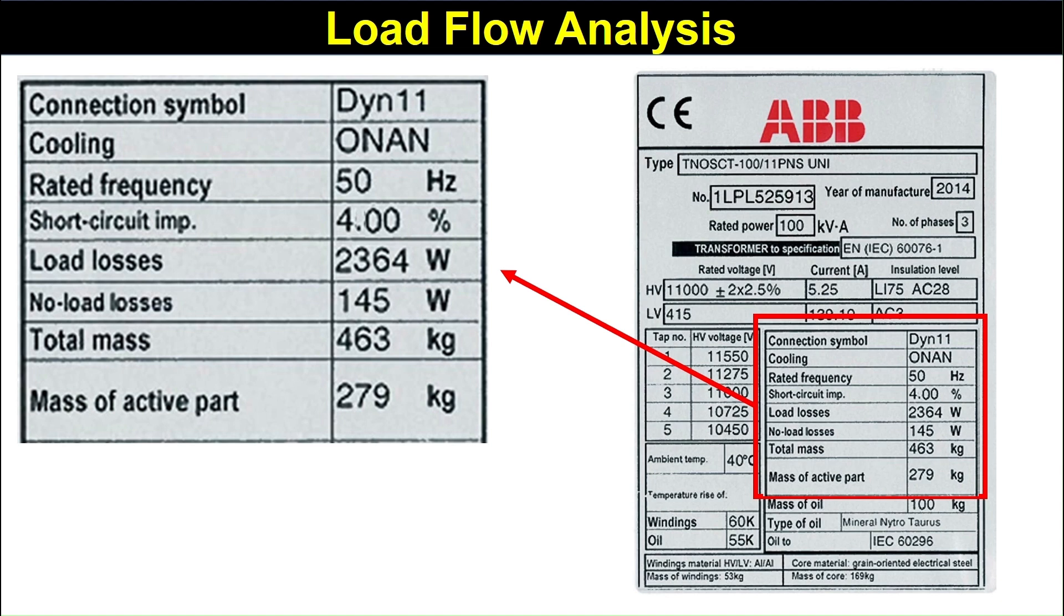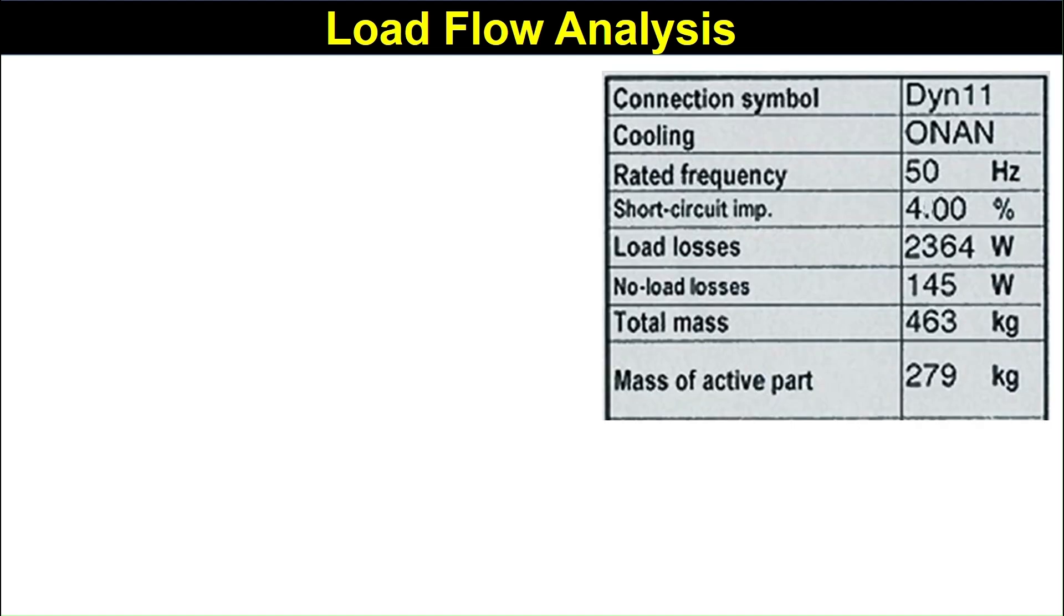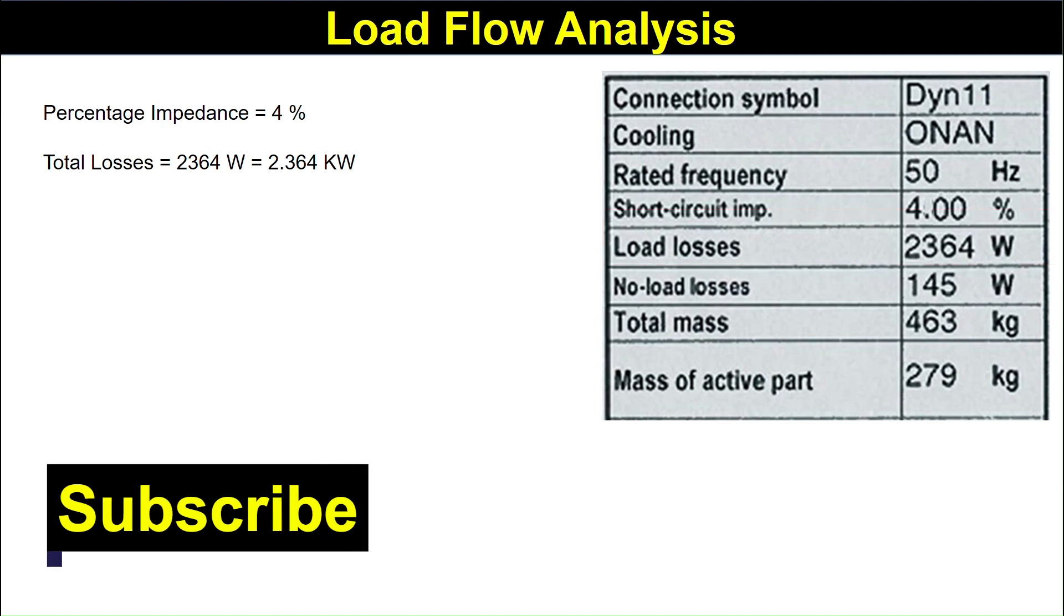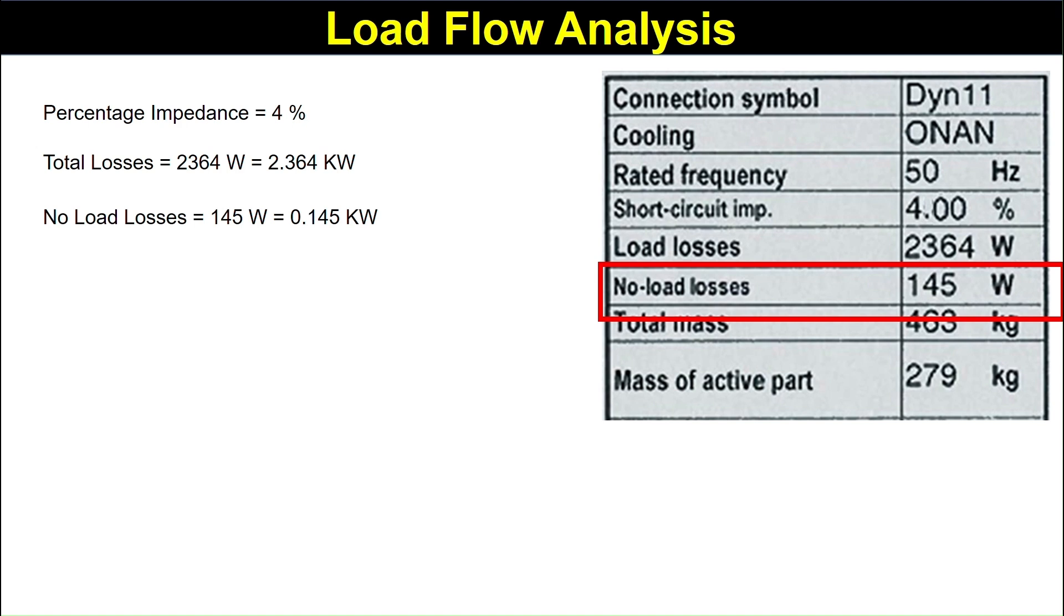How we calculate the X by R ratio of %X or %R? Percentage impedance is 4%. It is mentioned in the nameplate. Similarly, the total loss is 2364 watt which becomes 2.364 kilowatt. And no load loss is 0.145 kilowatt.